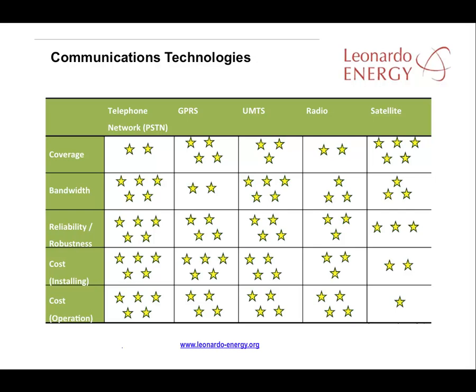Here we have a comparison table of technologies that could be used for remote communications. The more stars in a cell, the better the technology. While satellite offers the best coverage, it also comes with the highest installation and operation cost. UMTS cell phone technology is probably most recommended as the networks continue to spread and develop at a rapid pace worldwide. If there is telephone network coverage in the area of the PV facility, that might be the cheapest and most reliable way to communicate with the solar plant.